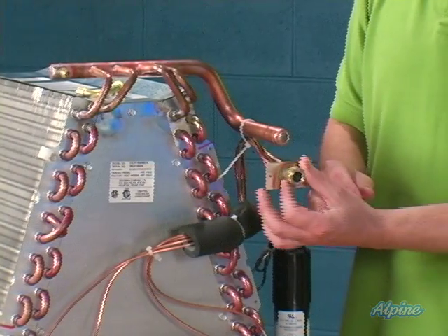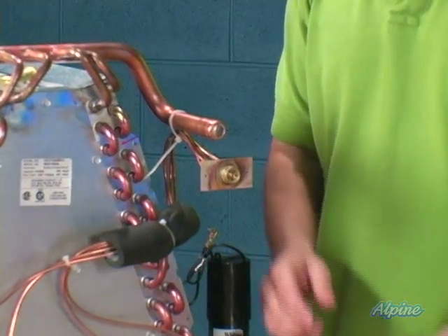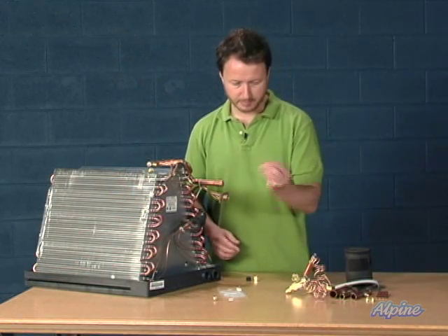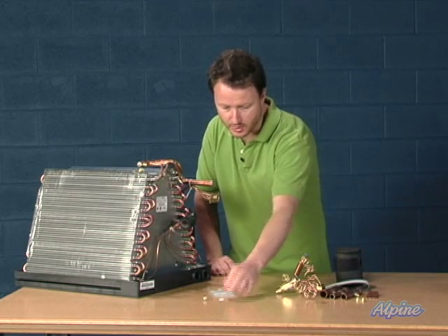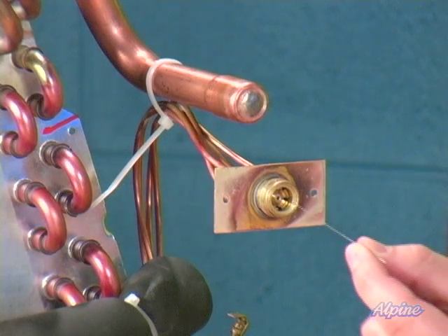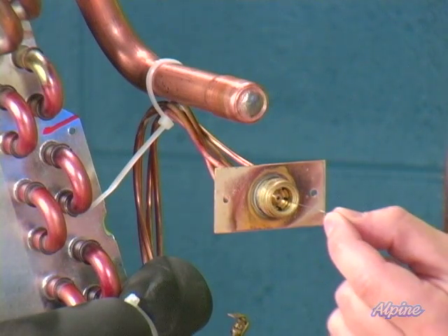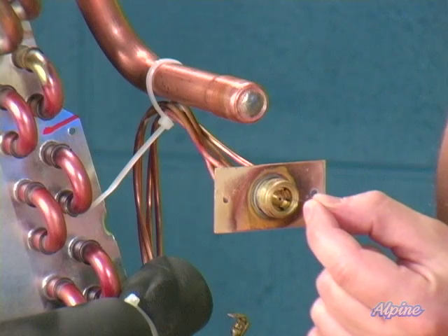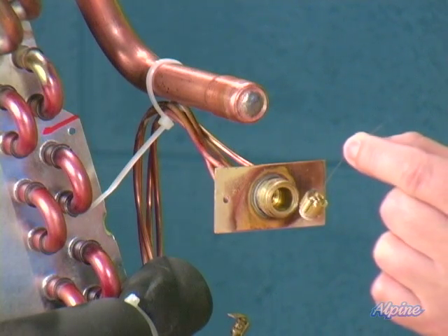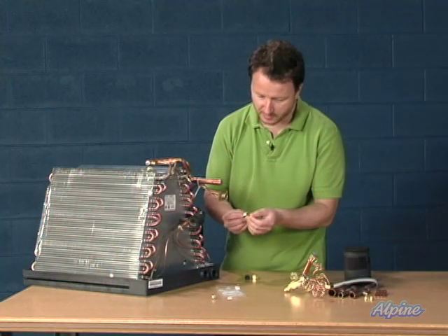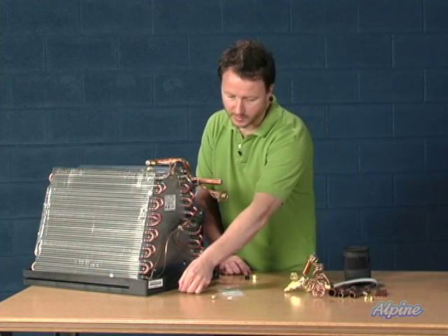So the first step is take this nut off, like so. This is just a little piece of plastic. We discard that. And inside here, you can see, is that orifice. Now, to make it easy to pull that out, the new orifice kit will have this little wire included, a tiny little wire, which you simply put through the center of that orifice and then whoosh, pull it out. That was easy, right? Okay. That will be discarded. Make sure you don't confuse the old one and the new one.